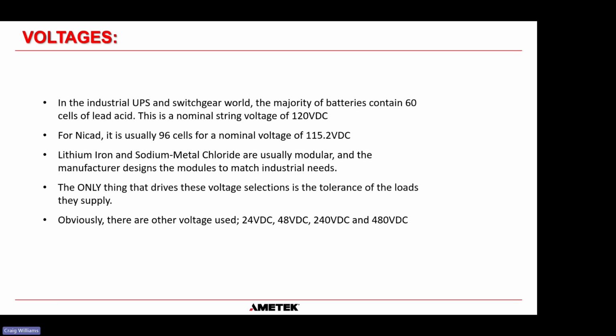So in the industrial UPS and switchgear world, the majority of batteries contain 60 cells of lead acid. And that's a nominal string voltage of 120 volts DC. Now, this is somewhat changing. There are some systems that operate at 240 volts DC, which would be 120 cells of lead acid. But historically, for switchgear systems and for industrial UPS systems, the nominal string voltage used to be 120 volts DC. That was a standard that was adhered to quite stringently historically, but it is changing now. For NiCads, that means you would usually use about 96 cells for a nominal voltage of 115.2.